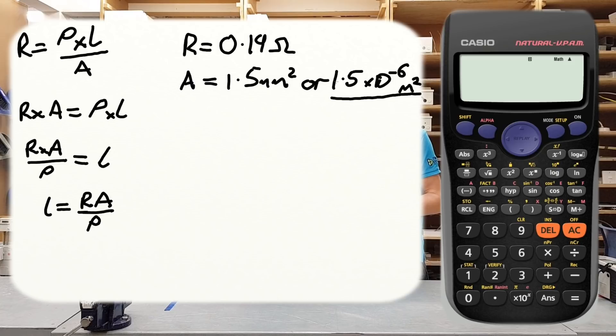If you're not sure why we've introduced this number now, because this is the number that we're actually going to put into our formula, please go back and watch my previous video on resistance and resistivity calculations. We're then going to look at our value for ρ, and this becomes interesting again. The material of the conductor was copper, which has a resistivity of 17.2 × 10^-9 ohm meters. So this is normally expressed as 17.2 micro ohm millimeters. Again, for an explanation as to why this has times 10^-9 at the end of it, please watch that previous video on resistance and resistivity calculations.